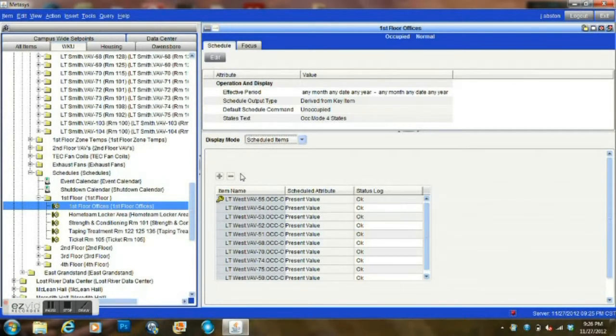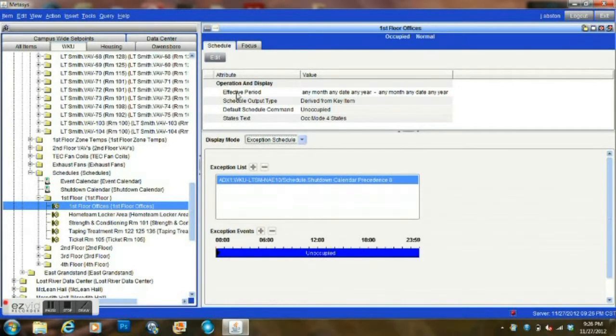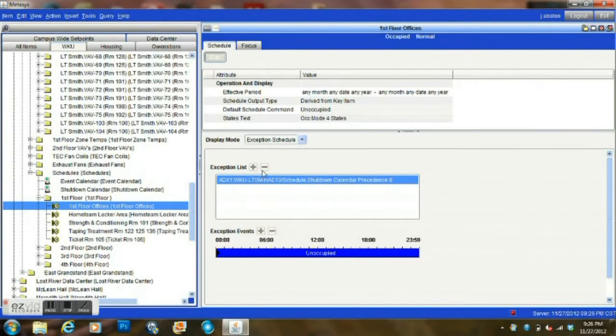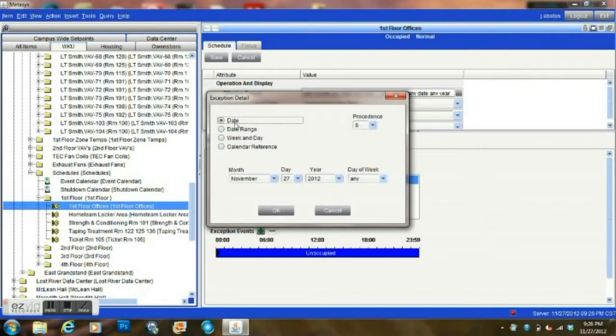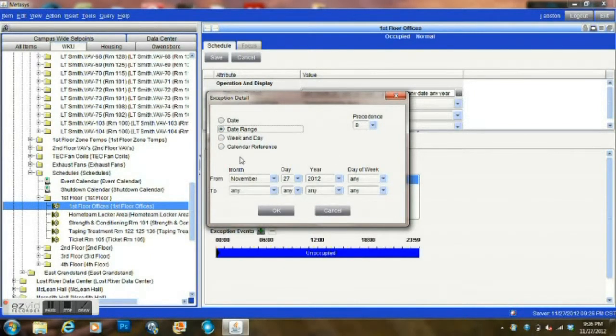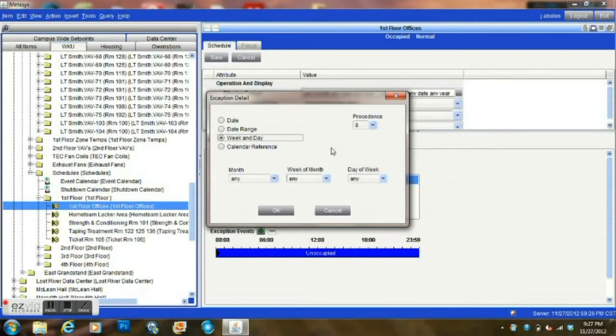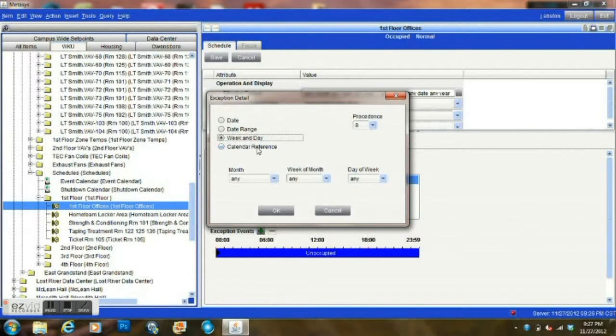One of the other features about schedules is during special event times. We can use the exception date where we can actually go in and enter a specific date. If we wanted to run the box for just a couple of hours tomorrow, we can go in here and set a particular date by the month, by the day, by the year, or even by the day of week. We can go a date range where we can have it run through a series of days. We can go a particular week and day. There's a lot of functionality on it.